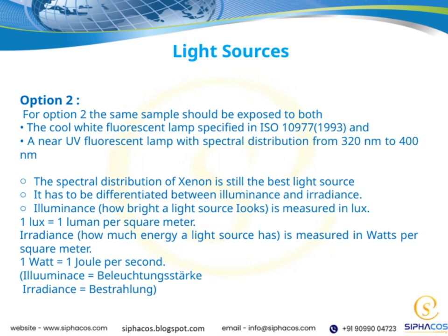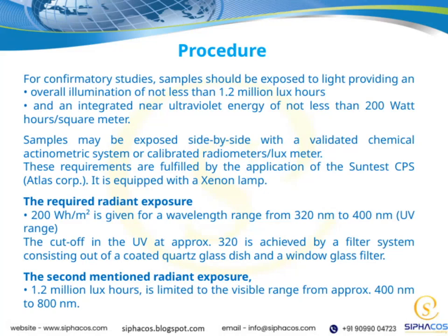energy impact. By carefully selecting and comparing these sources, we can better simulate real-world conditions and ensure our testing is as representative as possible of actual use cases. When we're conducting confirmatory studies, it's essential that our samples are exposed to a specific type of light to ensure consistency and reliability. The exposure must provide an overall illumination of at least 1.2 million lux hours.